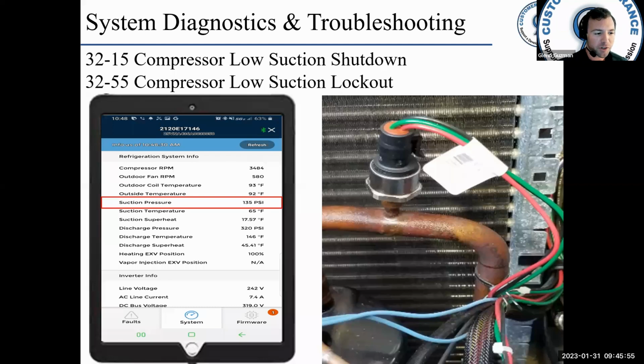Check your pressure and temperature difference of refrigerant lines at the condensing unit compared to the fan coil or the furnace coil. Maybe I've got excessive pressure drop in my liquid or suction lines somehow. So, if you have a metering device issue or you suspect a metering device issue, confirm your airflow first. That's refrigeration troubleshooting 101. Check your airflow first, then your components.